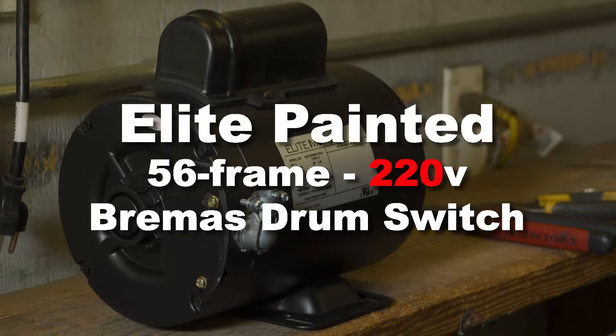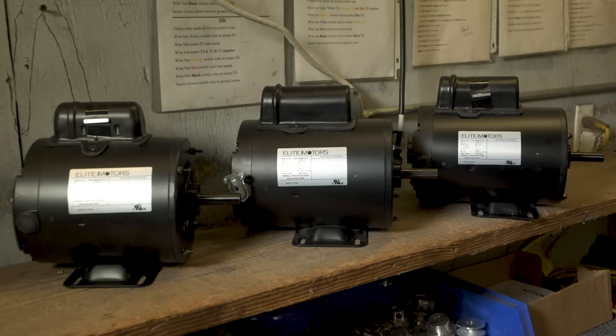In this video we're going to show you how to properly wire the Elite painted 56-frame, 1-horsepower motor to the Bremas brand drum switch for 220-volt use. Bremas brand switches with red handles are supplied by BHUSA. They are NEMA rated up to 20 amps and can be used on any BHUSA supplied single-phase reversible AC boat lift motor from three-quarter horsepower through one and a half horsepower, both 110-volt and 220-volt.